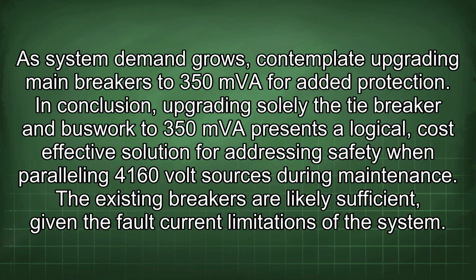In conclusion, upgrading solely the tie breaker and buswork to 350 MVA presents a logical, cost-effective solution for addressing safety when paralleling 4160 volt sources during maintenance. The existing breakers are likely sufficient, given the fault current limitations of the system.